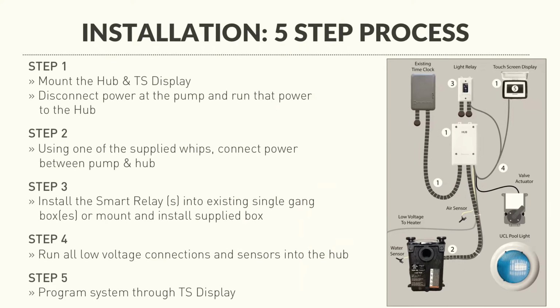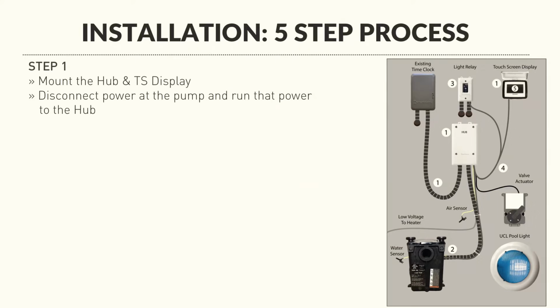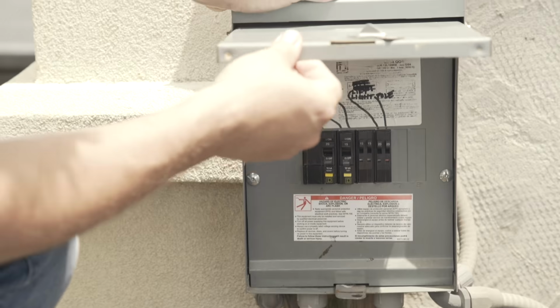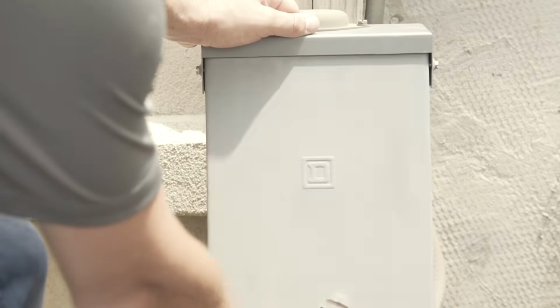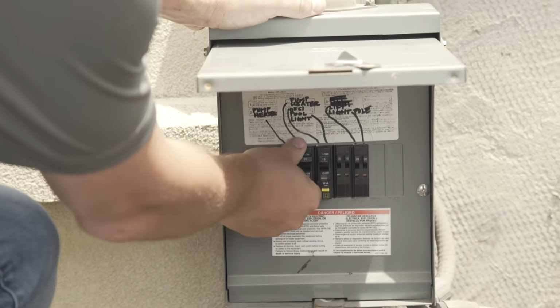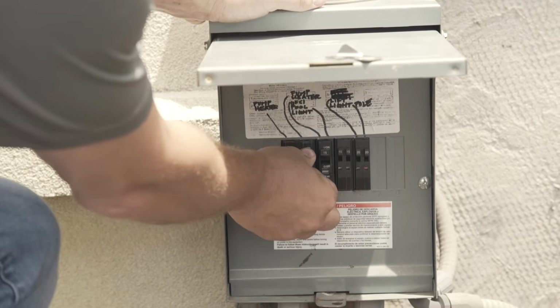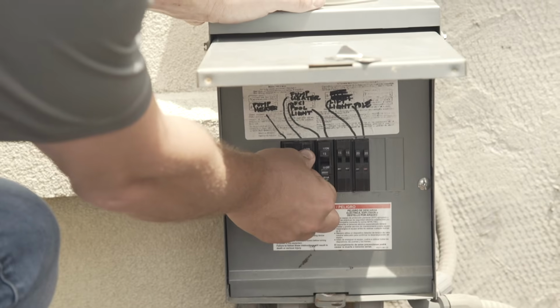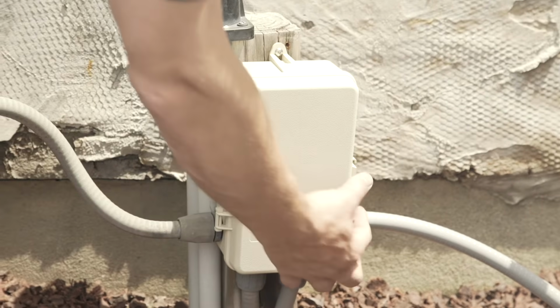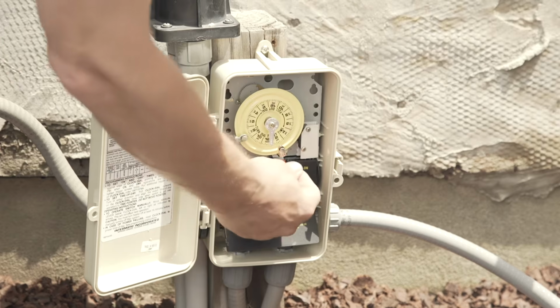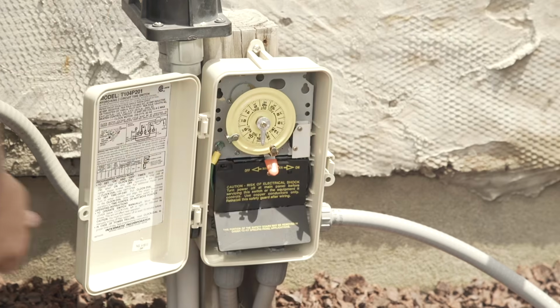5-step process. Step 1. Mount the hub and TS display. Disconnect power at the pump and run that power to the hub. Preparation. Before installation can be started, make sure to power off the equipment pad from the breaker. As an additional safety measure, also make sure the time clock is in the off position.